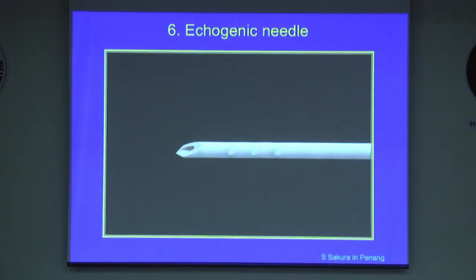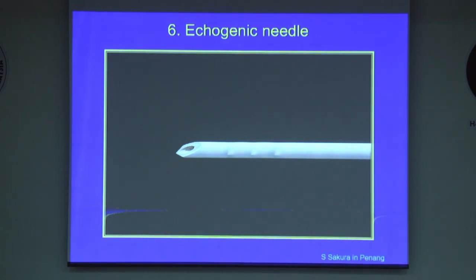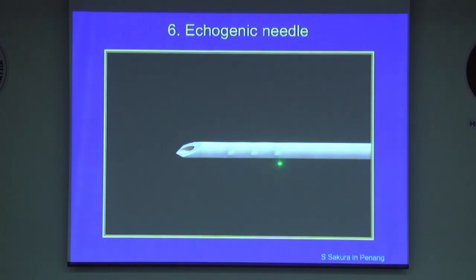The popularity of ultrasound-guided regional anesthesia has increased. Many instrument companies have come up with solutions to overcome the problem. These include echogenic needles. Echogenic needles use special coatings or corner reflectors to increase the reflection of ultrasound back to the transducer.